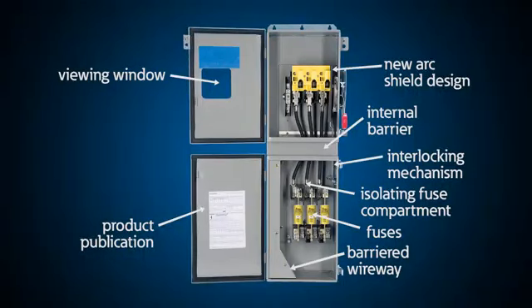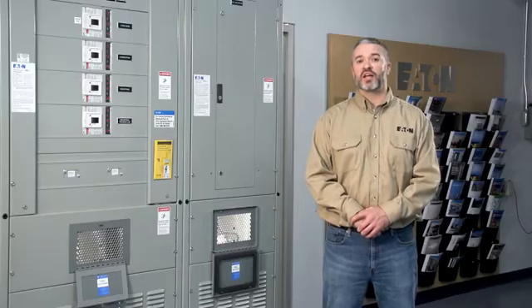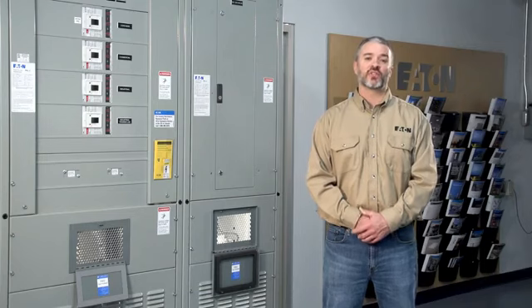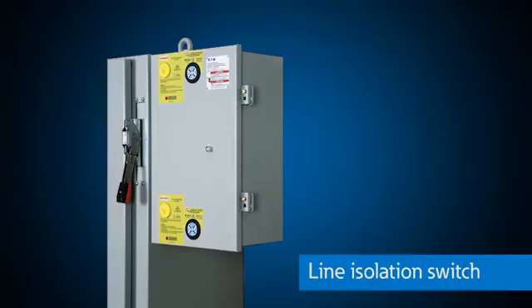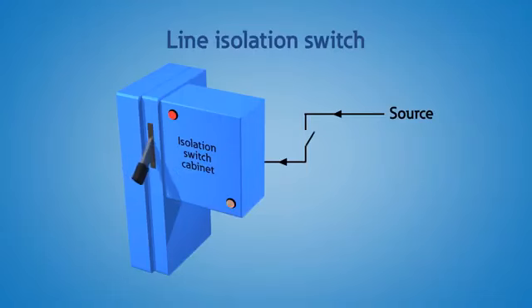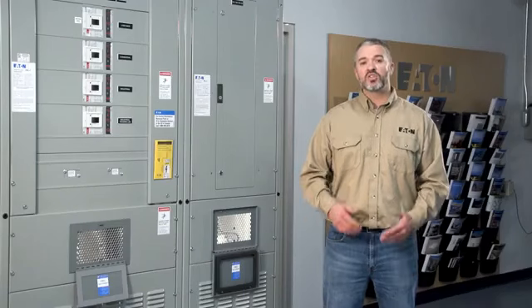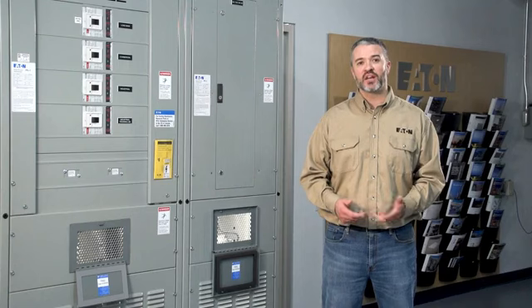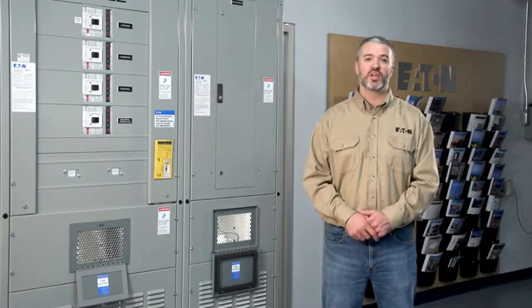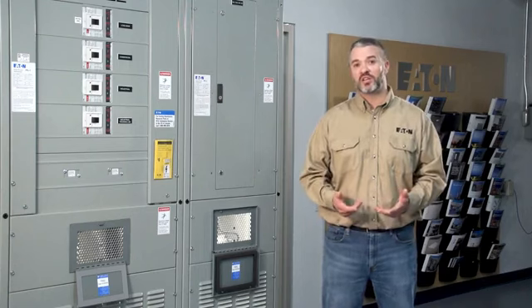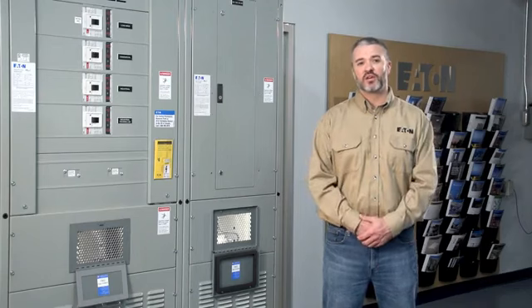This greatly reduces the risk, as you must consider the arc flash level of the source side even if the switch is in the open position with the door open on a standard switch. Anything that compartmentalizes electrical components generally helps with arc flash. This line isolation switch creates an external connection point for enclosed control cabinets, allowing you to lock out this switch and completely isolate the inside of the control cabinet. In most applications, the incoming breaker or connection point inside of one of these control cabinets has line voltage and again must be considered as live for arc flash considerations.